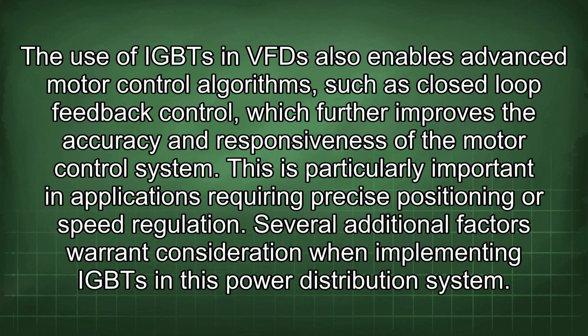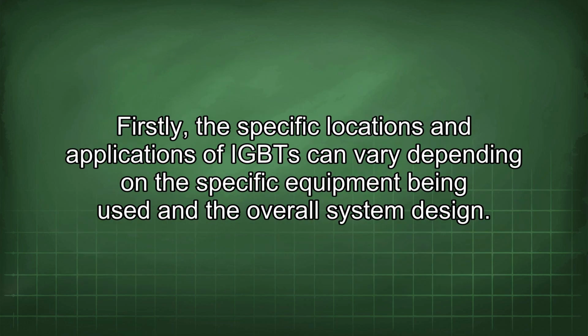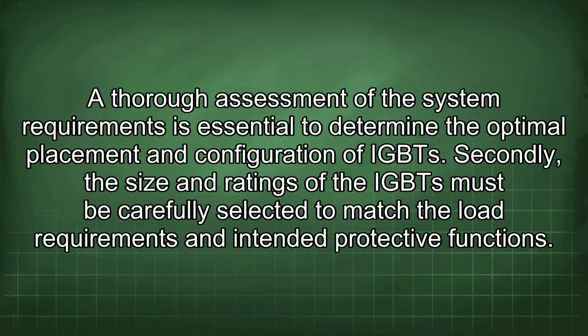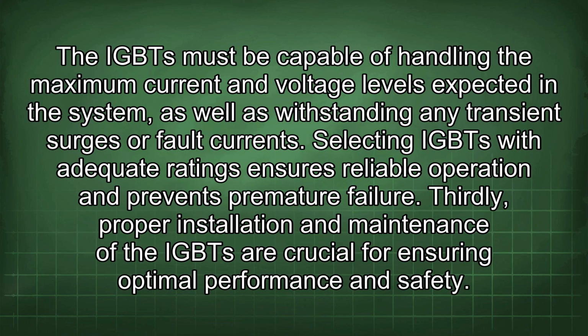Several additional factors warrant consideration when implementing IGBTs in this power distribution system. Firstly, the specific locations and applications of IGBTs can vary depending on the specific equipment being used and the overall system design. A thorough assessment of the system requirements is essential to determine the optimal placement and configuration of IGBTs. Secondly, the size and ratings of the IGBTs must be carefully selected to match the load requirements and intended protective functions. The IGBTs must be capable of handling the maximum current and voltage levels expected in the system, as well as withstanding any transient surges or fault currents. Selecting IGBTs with adequate ratings ensures reliable operation and prevents premature failure.